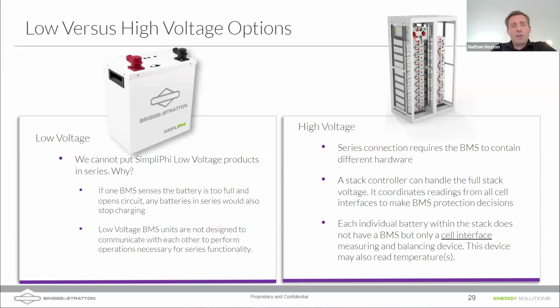Typically, a low voltage system under NEC code refers to nominal systems 48 volts and below. Once you get into higher voltages, different NEC codes apply. We do make high voltage stacks -- what I'm showing on the right side of the screen is a high voltage stack, where these batteries are actually placed in series. I want to highlight that we never place low voltage battery systems in series. The balance of system equipment inside that BMS does not function appropriately if the charge controller is running in series through the batteries.